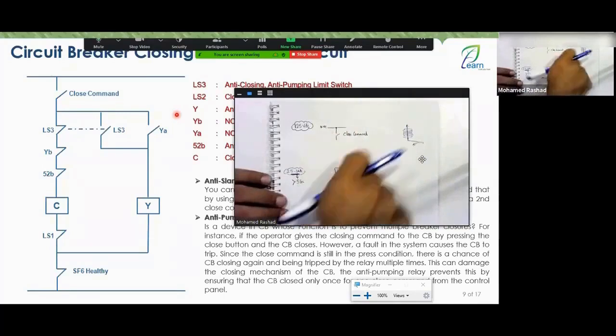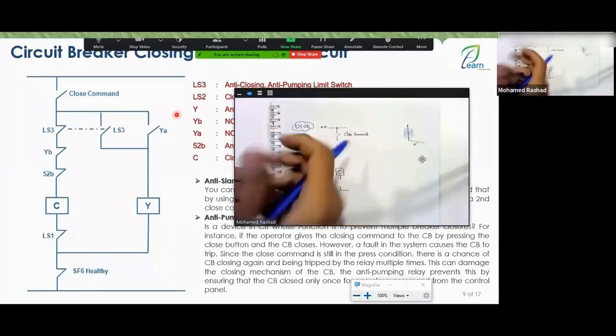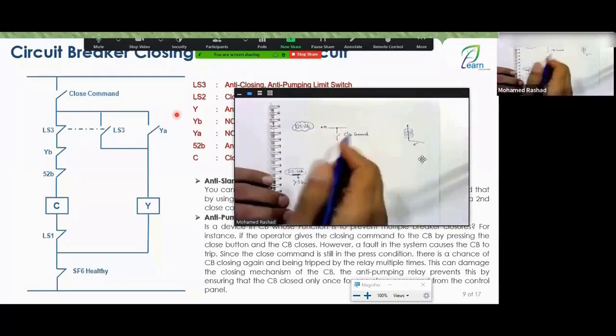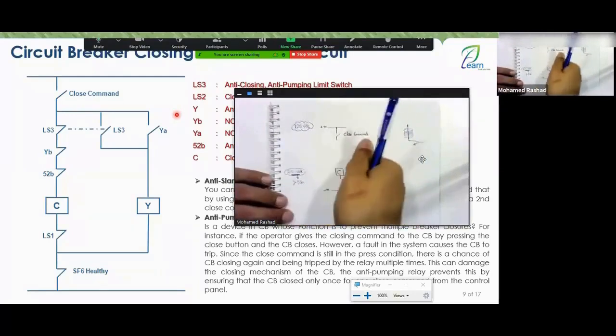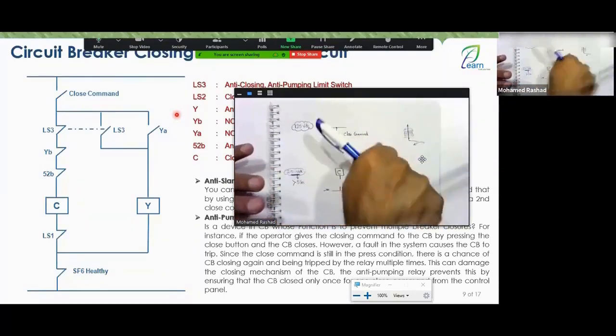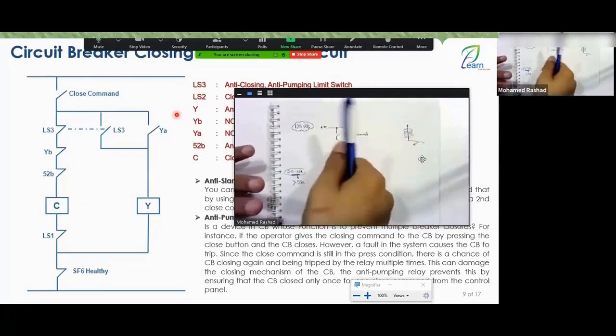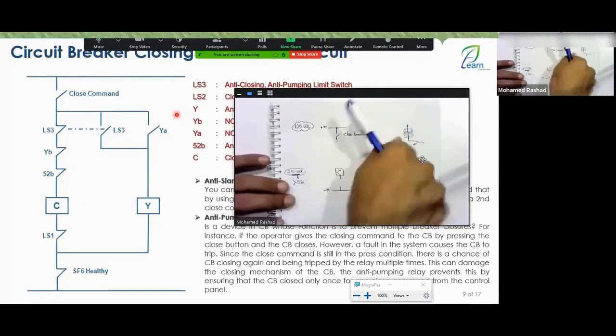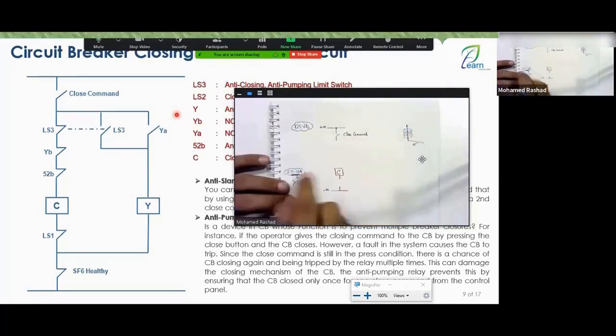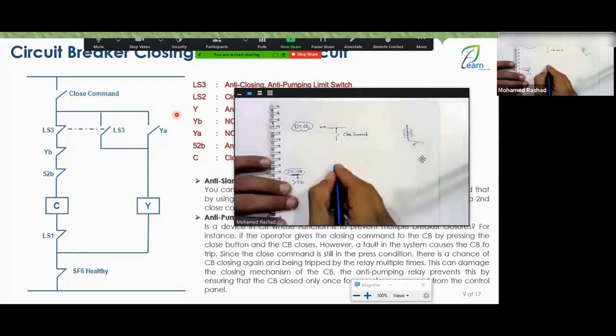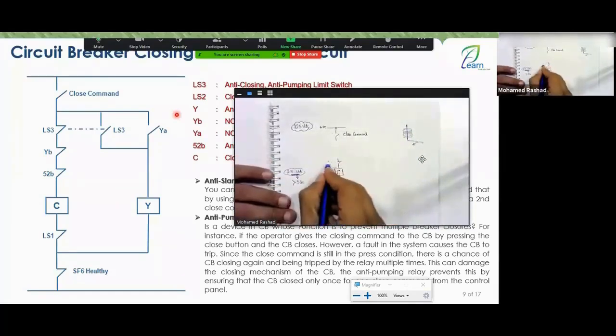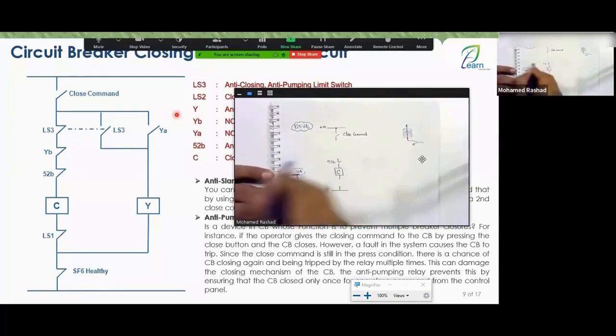It will give a close. The hand is trying to close the breaker, but it's not closing. He's not even aware that it's already closed. So he keeps trying to close it, thinking there's a problem, that it's not making good contact or not closing properly. As a result, he keeps doing this with his hand several times until the closing coil burns out. That's why, what did he do? He came here before the closing coil and took a contact here, a normal close contact from the electrical breaker, called 52B.